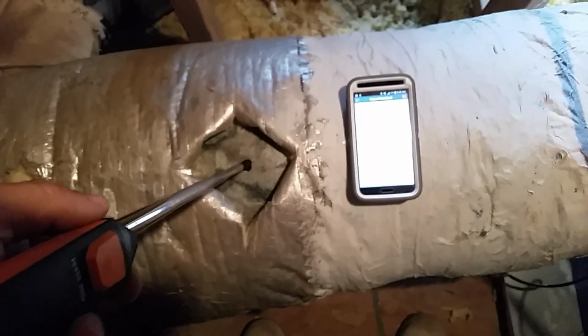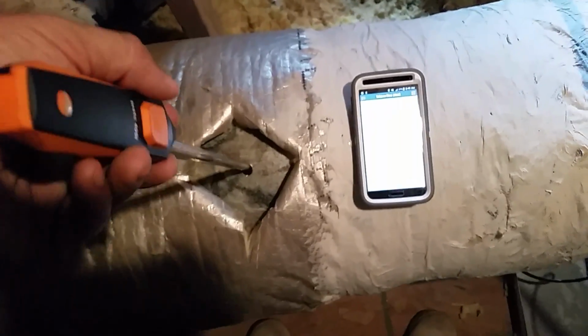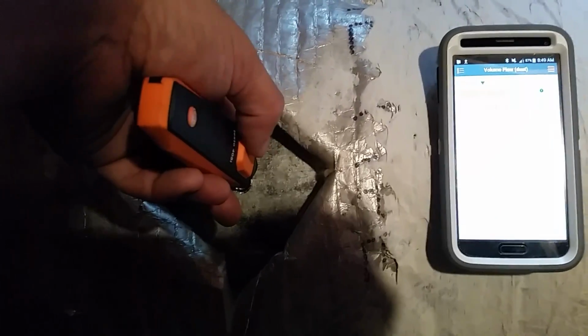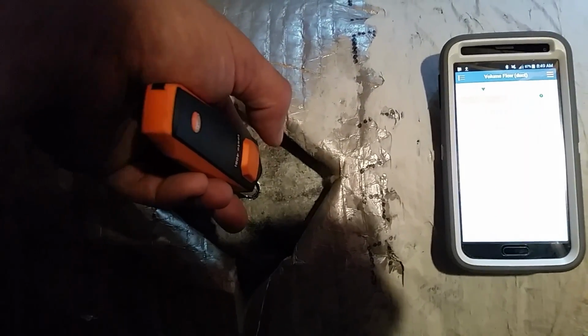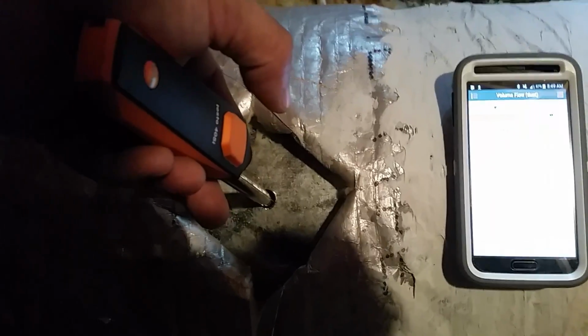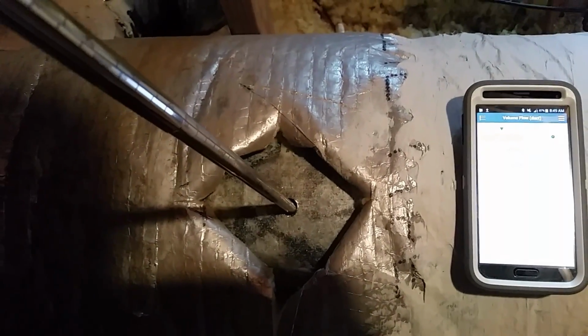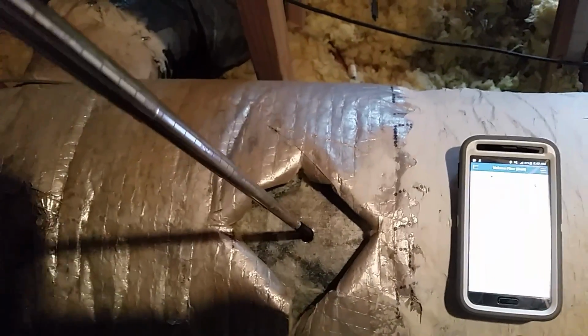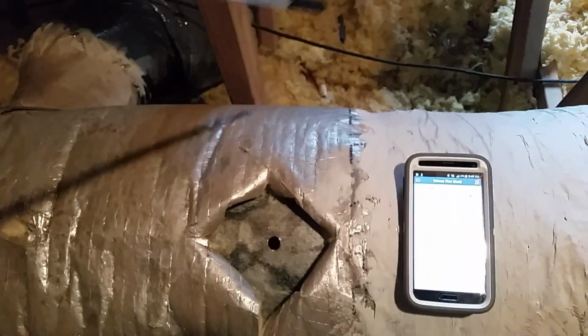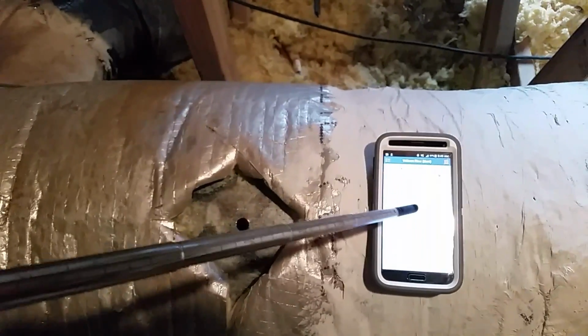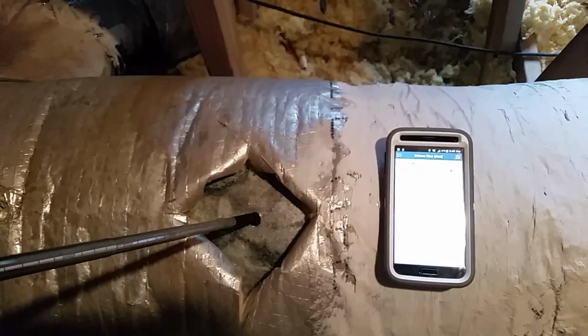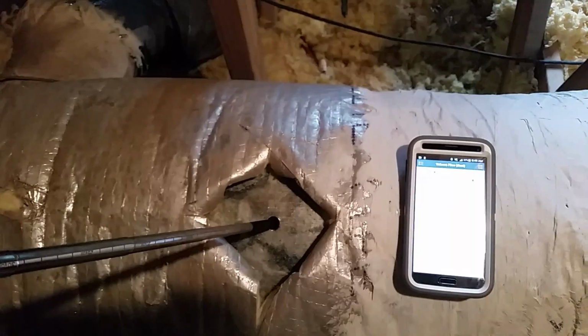What you're going to do is insert this down into the duct all the way to the bottom. And once you're at the bottom and you're ready to go, you're going to hit play, and you're going to slowly and consistently draw the 405i back out of the duct. Once you get to the top of the duct, you're going to hit pause on the button, and that's going to be how you take your reading. We'll do that about 4 times, and we'll see what kind of readings we get.